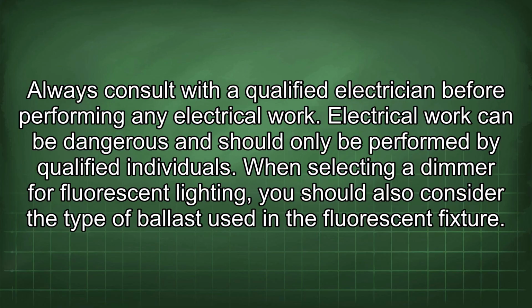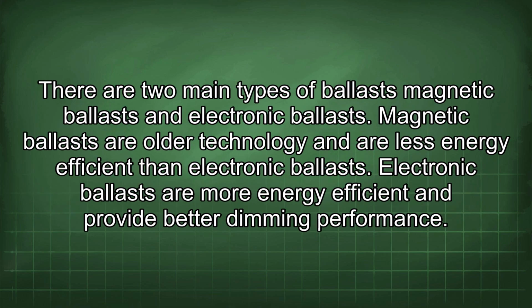When selecting a dimmer for fluorescent lighting, you should also consider the type of ballast used in the fluorescent fixture. There are two main types of ballasts: magnetic ballasts and electronic ballasts. Magnetic ballasts are older technology and are less energy efficient than electronic ballasts. Electronic ballasts are more energy efficient and provide better dimming performance.